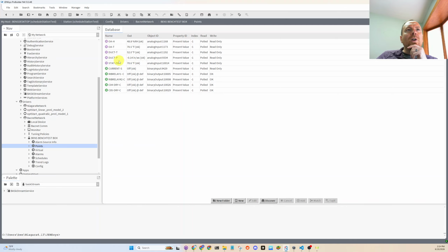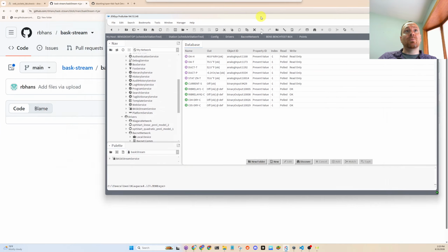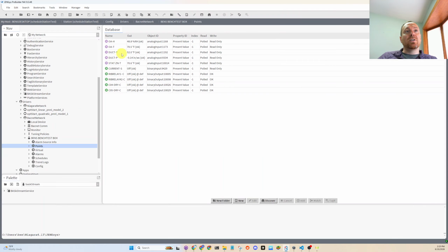What I've been doing is polling from this Windows computer, the same Windows computer I'm recording this YouTube video on, which is running the Niagara station, and I can pull the sensor data. This is real live sensors. And yes, the duct temperature out of my air conditioner right now is 51 degrees. It's freezing. It's a very terrible little HVAC system I have in this office I rent.